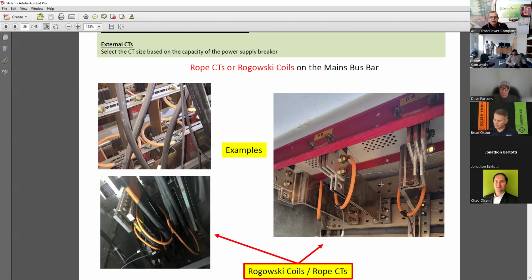So they took a power shutdown and installed it in the wrong place, and all the data we were getting was wrong, because there's another set of CTs measuring the load on the hospital. So now both the CTs that they installed externally and the CTs inside the MPTS have the same reading. All the data we were gathering was the same from both sides, so MPTS thinks there's nothing to do because it's a perfect condition.